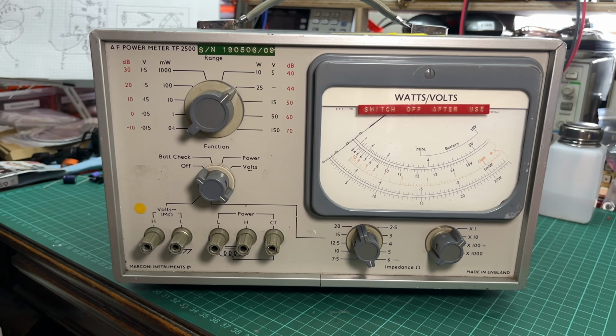We'll see what condition they're in, and then we'll go from there and disassemble the case of the instrument, have a look inside, see what it looks like. One really nice thing about this is, even though it's got quite a late calibration, the calibration seals on the back are intact, so I'm kind of hopeful this one hasn't been monkeyed about. Okay, let me turn it round and then let's get the batteries out.